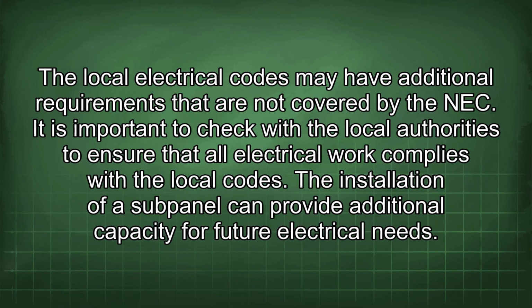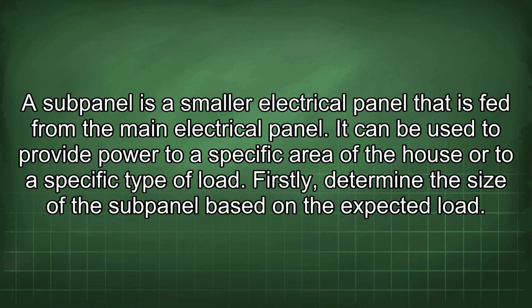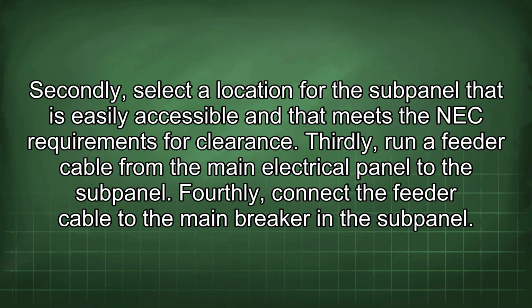The installation of a subpanel can provide additional capacity for future electrical needs. A subpanel is a smaller electrical panel that is fed from the main electrical panel. It can be used to provide power to a specific area of the house or to a specific type of load. Firstly, determine the size of the subpanel based on the expected load. Secondly, select a location for the subpanel that is easily accessible and that meets the NEC requirements for clearance.